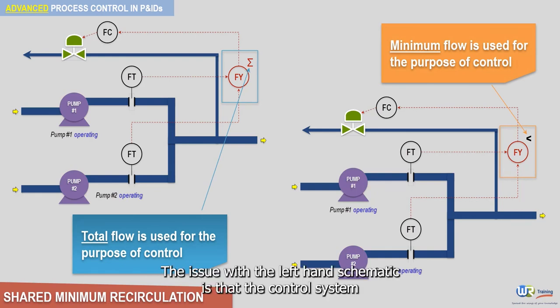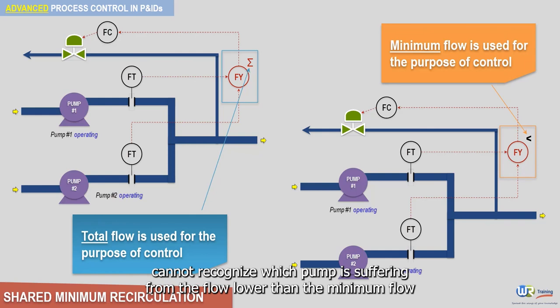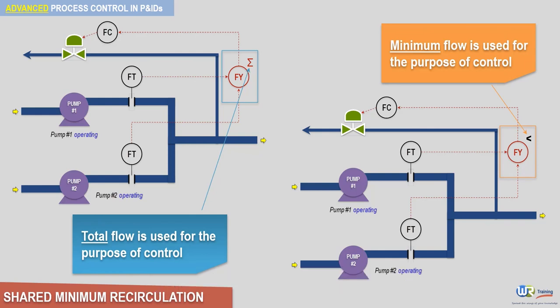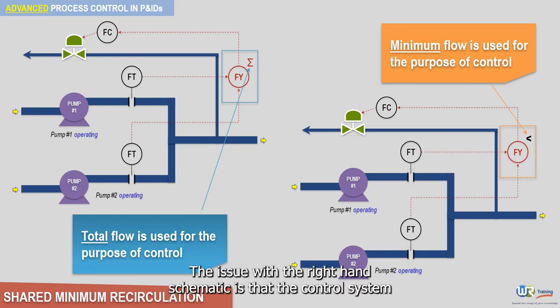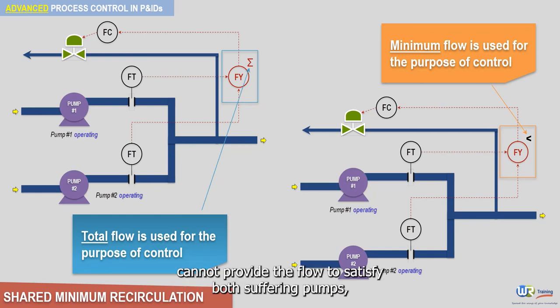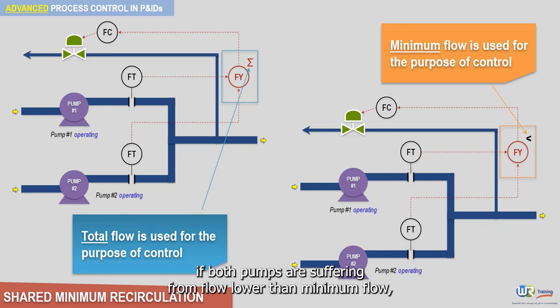The issue with the left-hand schematic is that the control system cannot recognize which pump is suffering from flow lower than the minimum flow. The issue with the right-hand schematic is that the control system cannot provide the flow to satisfy both suffering pumps if both pumps are suffering from flow lower than minimum flow, but with uneven difference to the minimum flow.